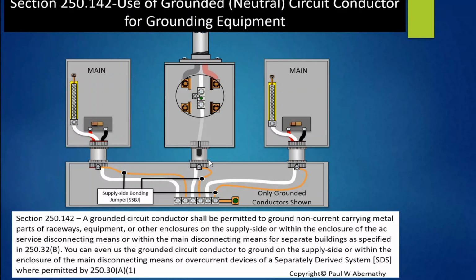Okay? Now, what about this enclosure? This enclosure right here, these are the conductors that are supplying it. So if this was a factory installed jumper, then I wouldn't have to do anything. It's supplied by the factory. But chances are, this here is a trough or wireway, and it's probably the wire type, so you're going to have to size it. You're going to size it based on the size of these service entrance conductors that are coming in that could potentially energize this wireway. Now, what about this one over here?